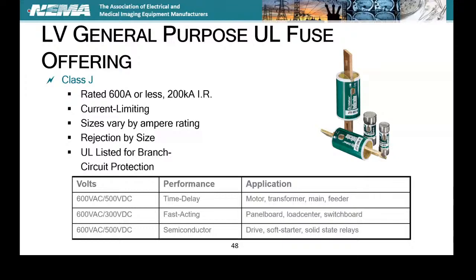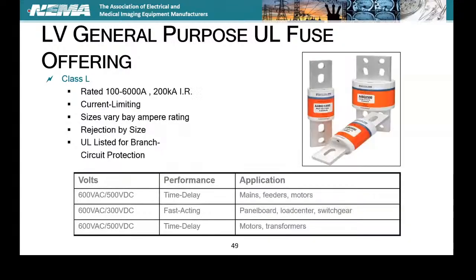So remember, some of them had the notches, some of them will reject based upon the size. And again, you have your time delay for motors and transformers. Fast acting is in your panel boards, load centers, switchboards, things of that nature. And then you have your semiconductor fuses, which are for those soft starters and solid state relays. The semiconductor fuses are sized based upon how much energy they let through, not necessarily by a branch circuit rating. They size those on how much energy they'll let back down to the load.